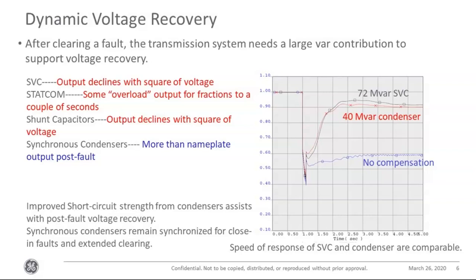And this is an example here where it's on a small system. There's roughly 200 megawatts load, half of which is induction motors. And you can see that, of course, with no compensation, which is in blue, there is no voltage recovery. Now, the condenser and SVC give comparable response, but you will notice that the condenser has to be of a much smaller rating.